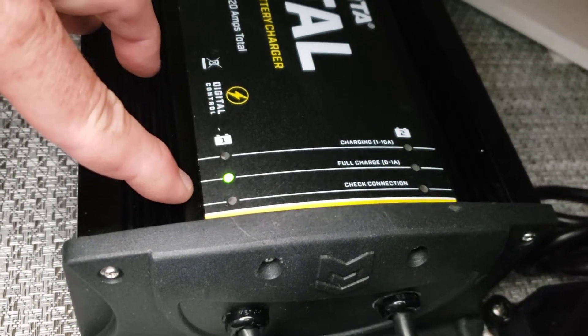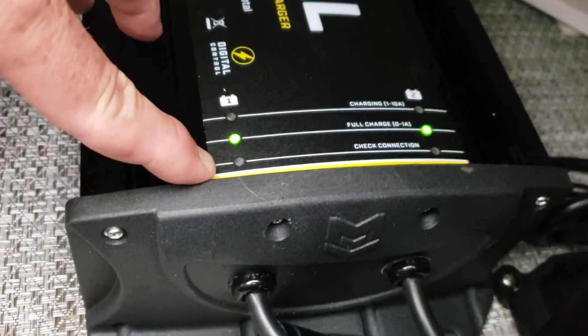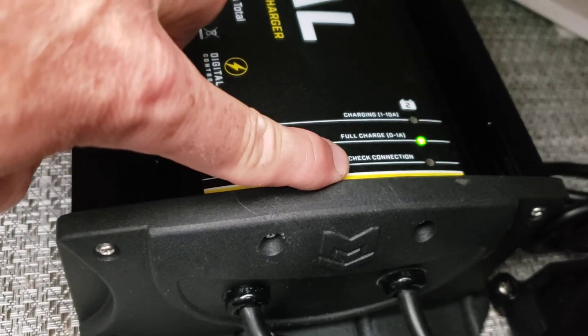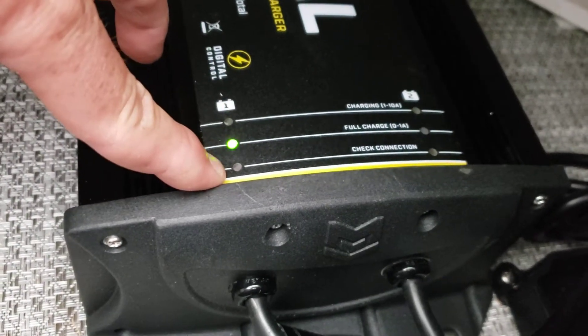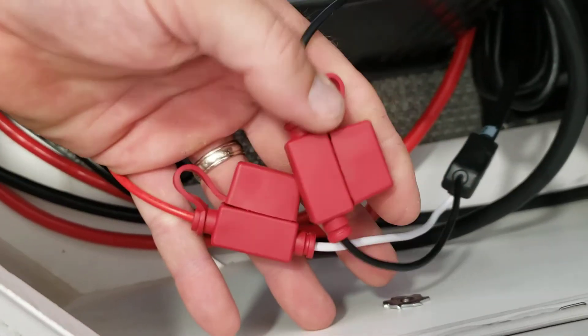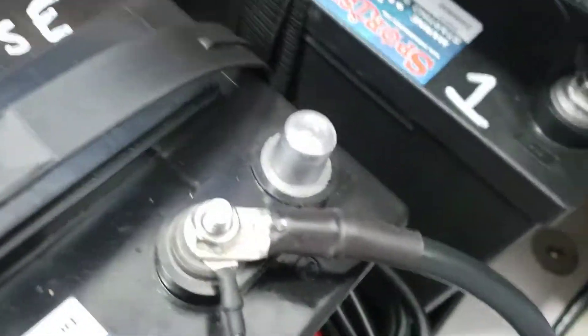In the second row down, and then the third row here is labeled check connection. That would be a red light that would indicate that possibly the fuses are blown, and each battery has a fuse on the positive and negative.